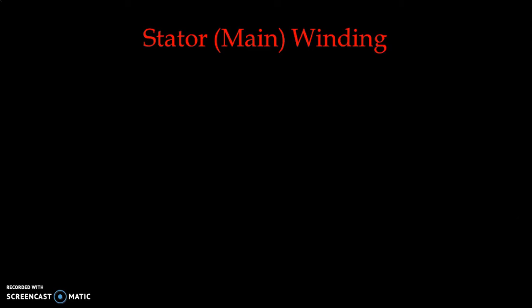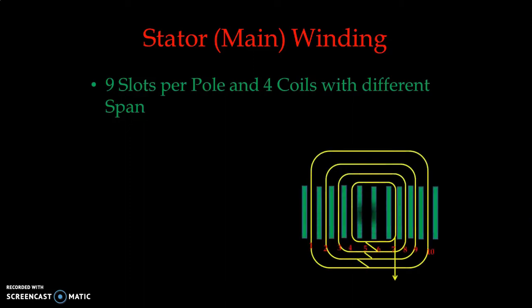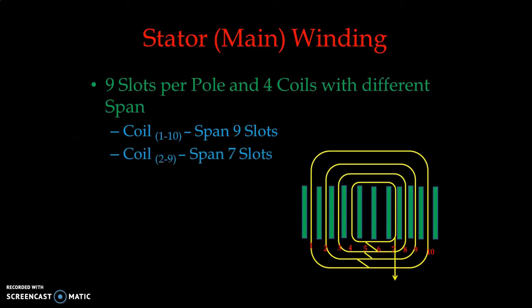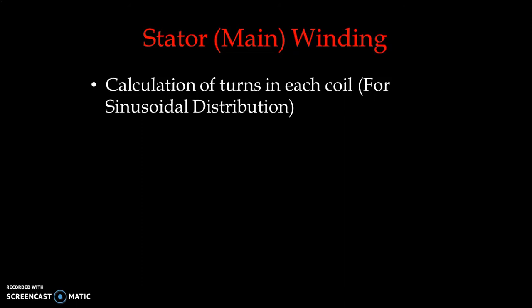These are the outermost coil of the adjacent pole group. Now let us take one stator winding arrangement. We have considered nine slots per pole and four different coils with different span, and we have reproduced our arrangement for ready reference. Coil 110 has a span of nine slots, coil 29 has a span of seven slots, coil 38 has a span of five slots, and the innermost coil 47 has a span of three slots.